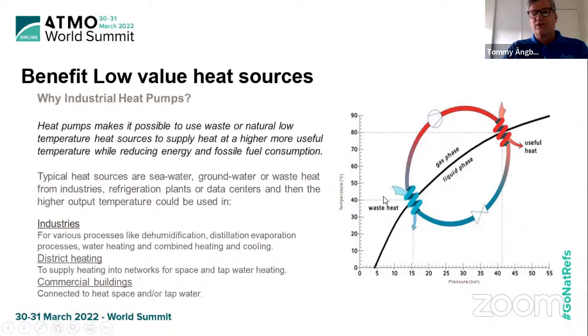The fascinating part is that by using heat pumps, we can take this low waste heat. If you see on the figure to the right, you have a waste heat at a temperature that maybe is not so valuable, and that you can increase to a higher level with a refrigerant circuit, where you have a refrigerant circulating, and where you can obtain the waste heat, and the gas is going through the compressors, and you get a higher pressure, and there you can take out the heat at a higher temperature. In this case, we are working in Celsius degrees now.